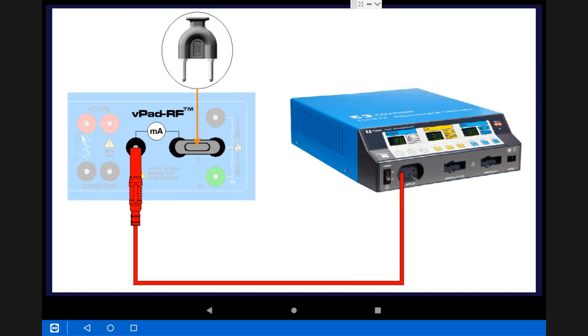Our final step here is going to be to do the leakage testing, where again, now you can see we've integrated with an image of the actual Force FX, just so you can see that we can have variation or change the devices and things like that. Once it's been connected, again, we'll set it back to precise and 70 watts. The next step, and again, we're in tolerance, it automatically passes to the next step.